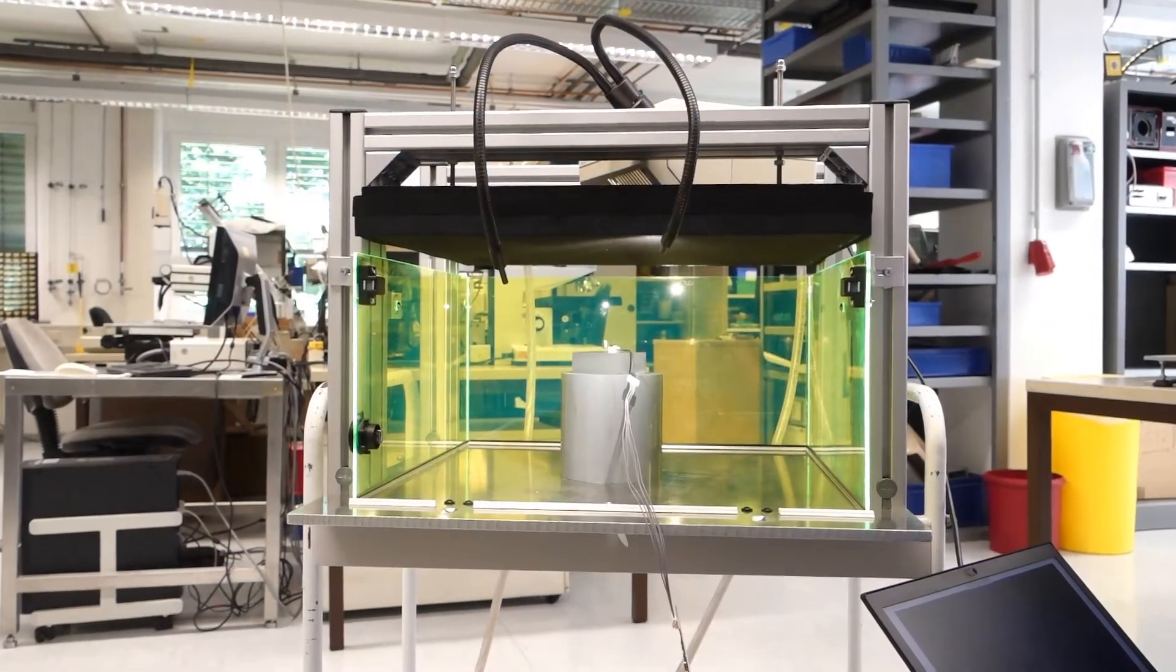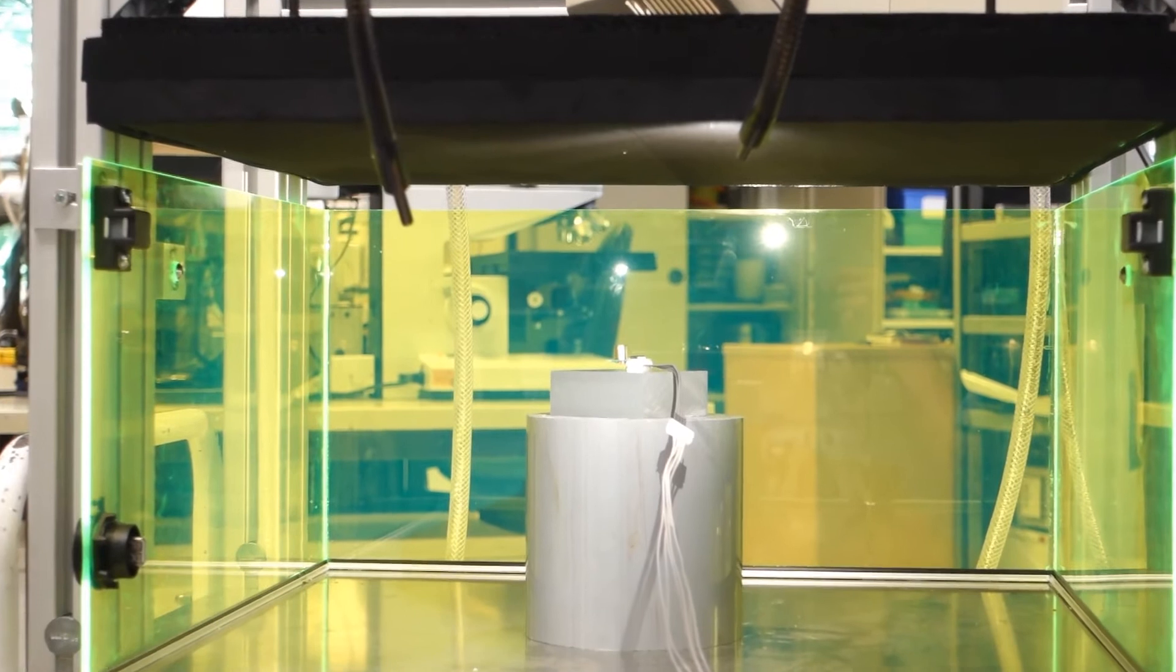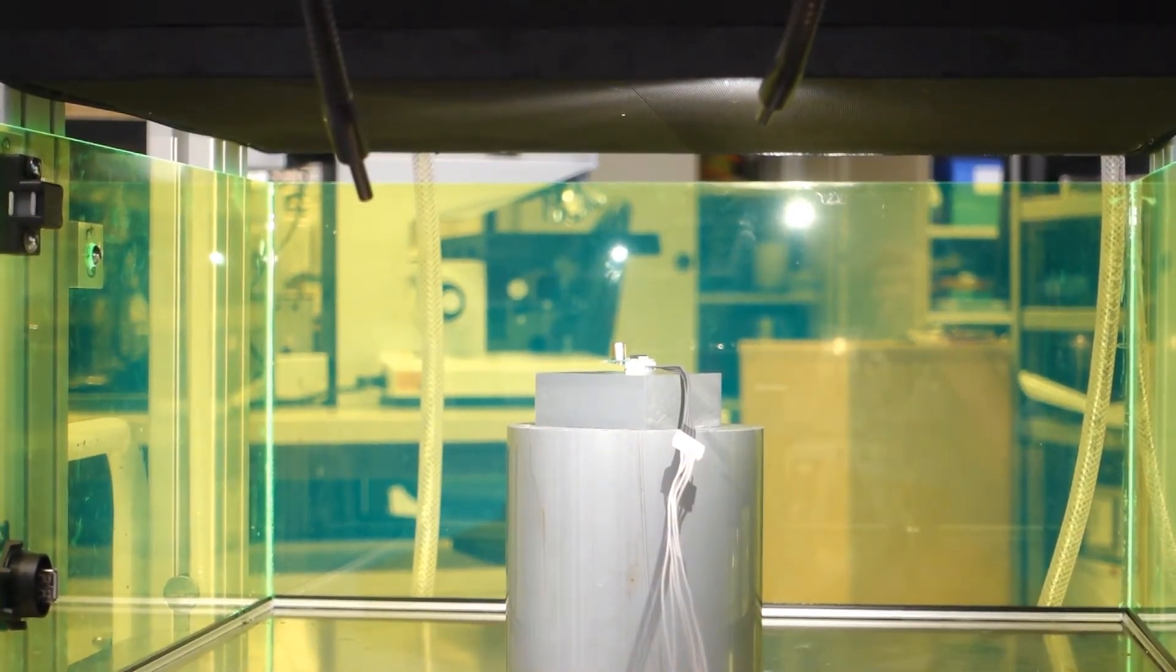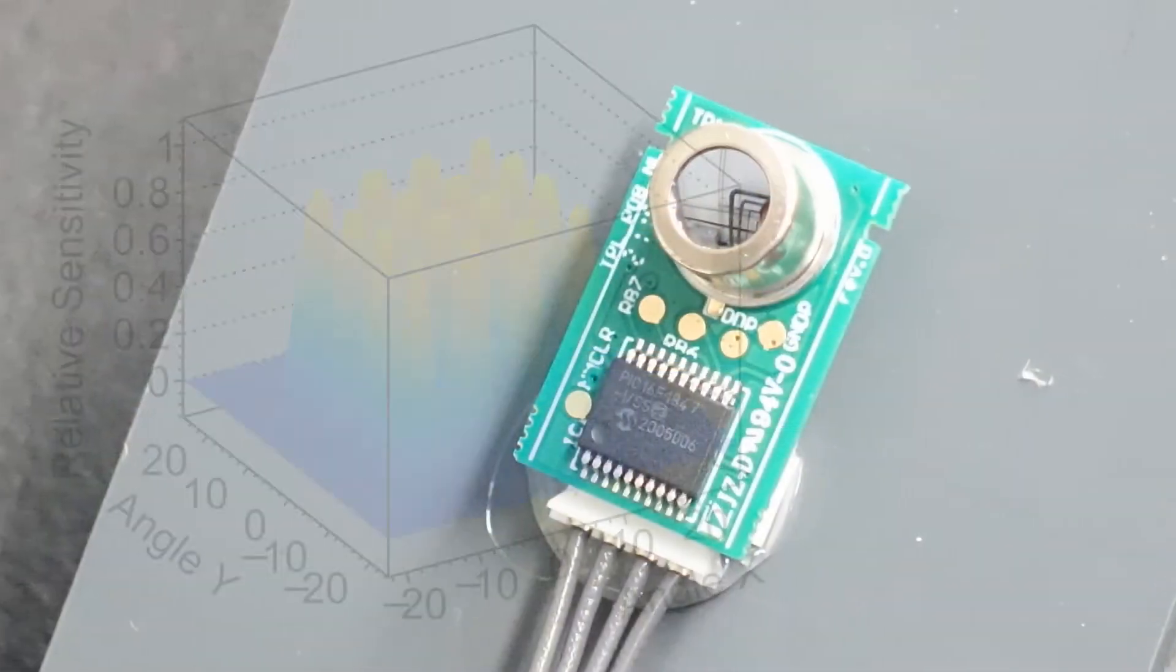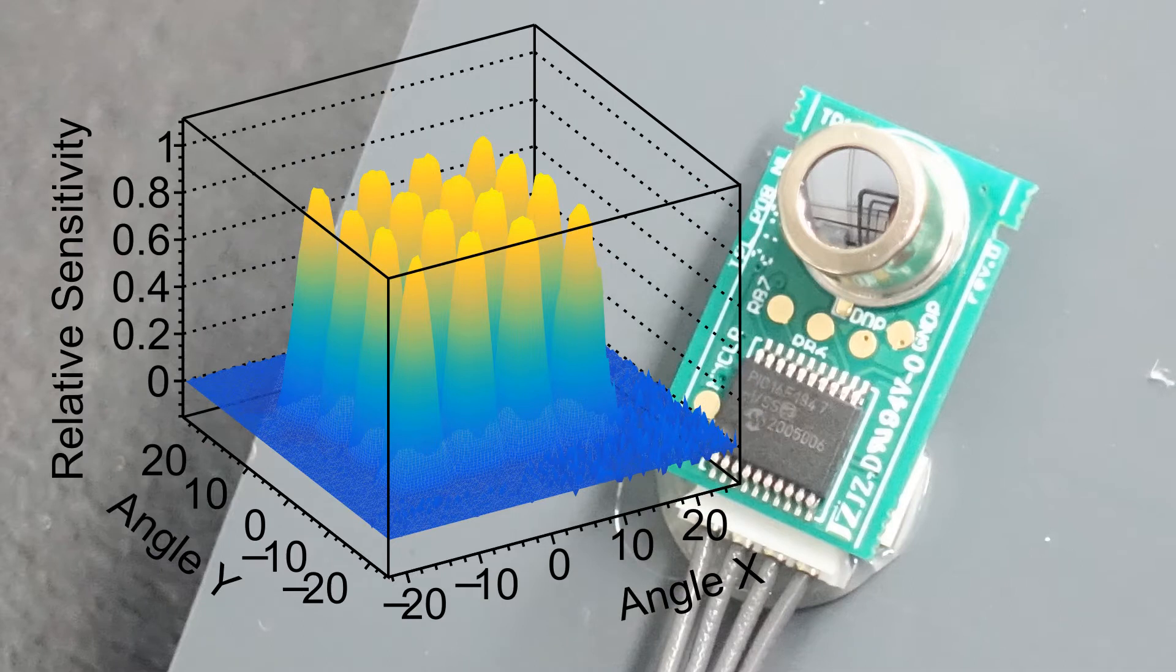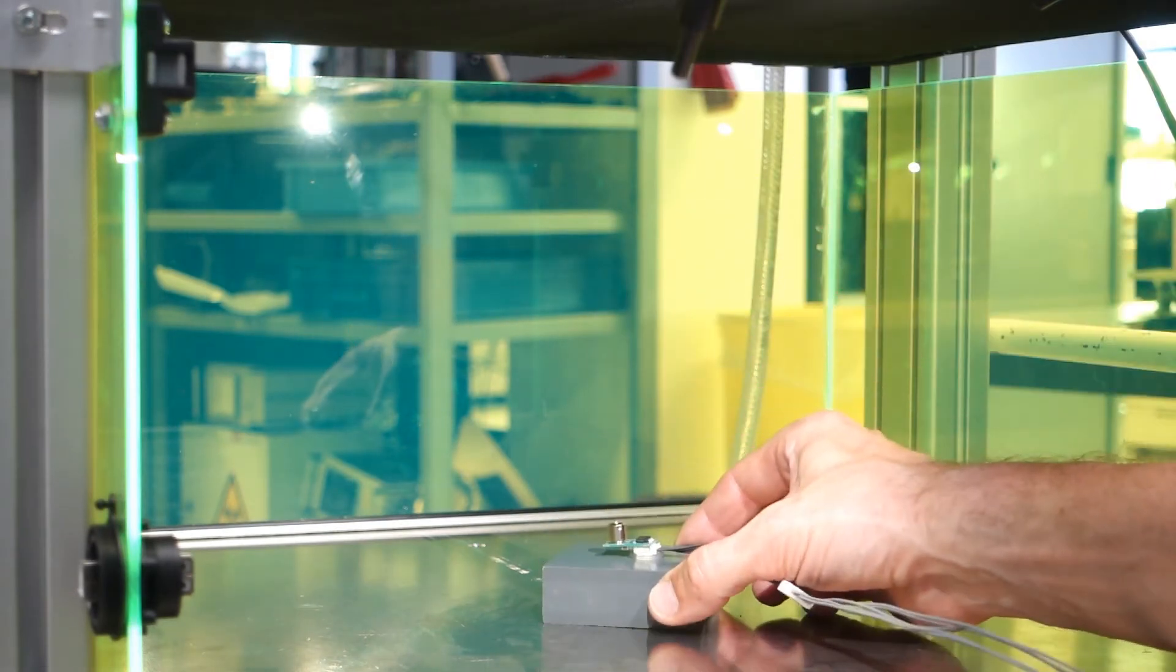To demonstrate what I'm talking about, we show in this video the temperature readings of a sensor which is facing upwards. Above the sensor, we have installed a temperature-controlled big area blackbody. As an example for all sensors, we have here a 4x4 pixel array with a narrow field of view. The blackbody surface is fully covering the sensor's field of view at all times.